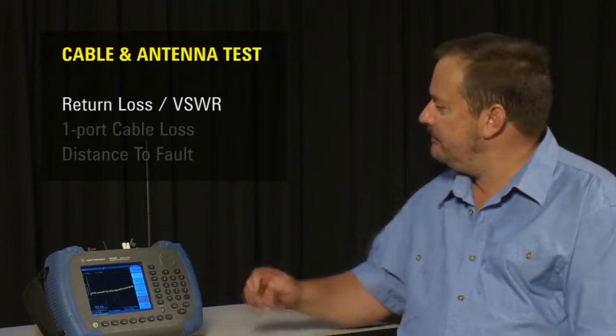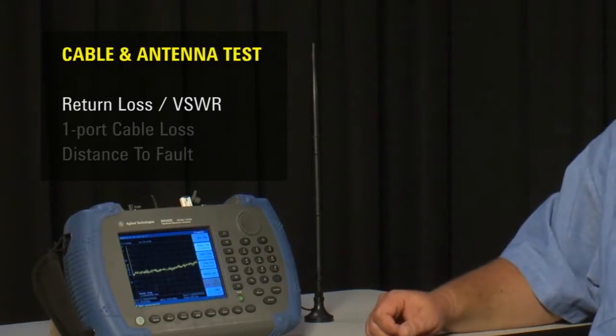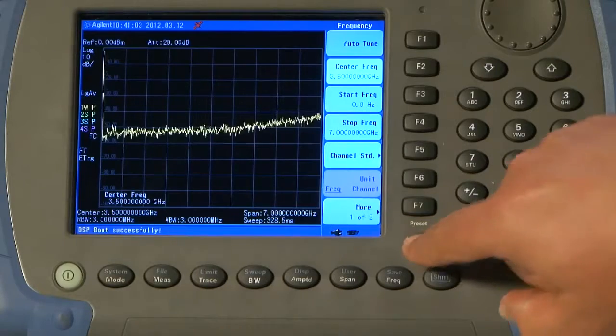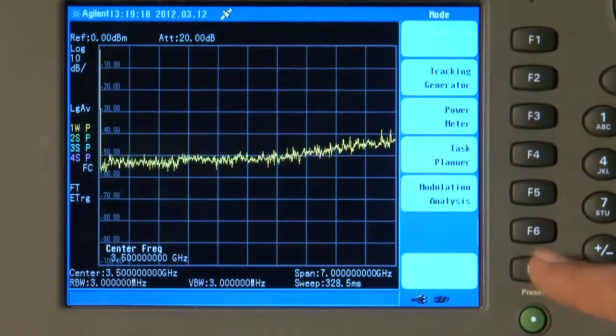Let's start by measuring the return loss and VSWR of this Wi-Fi antenna I have here. First, we will press the green preset button to put the instrument back to its factory default state and clear any strange settings that a previous operator may have used. Then press Mode, Cable and Antenna Test.